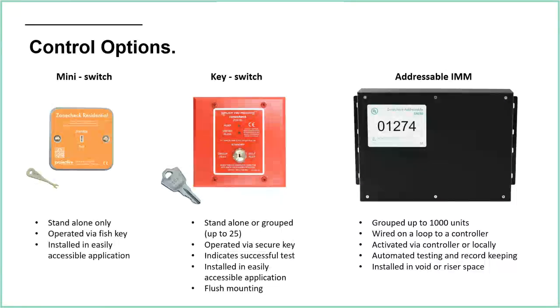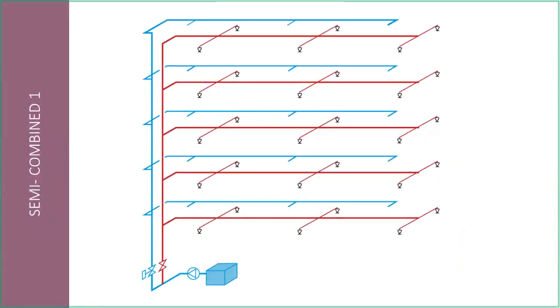Or we have our addressable system, which means that you can test all of the flow switches in a building through one controller unit. That system will also monitor the isolation valves on the floor as well, if they are compatible. What I should have said was, if the valves that are used are monitored valves, then they can be taken onto our system as well. So, three different control options for our residential zone checks. Do get in touch if you want to know any more.